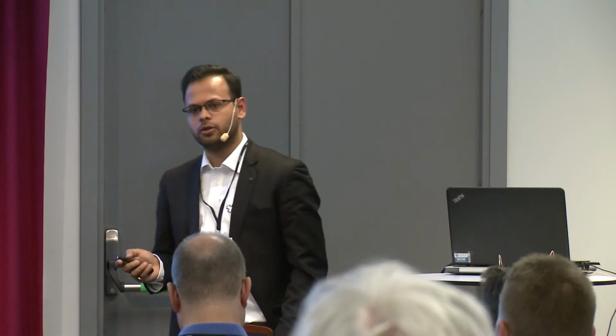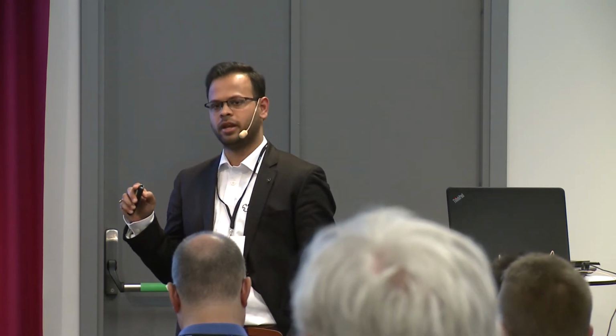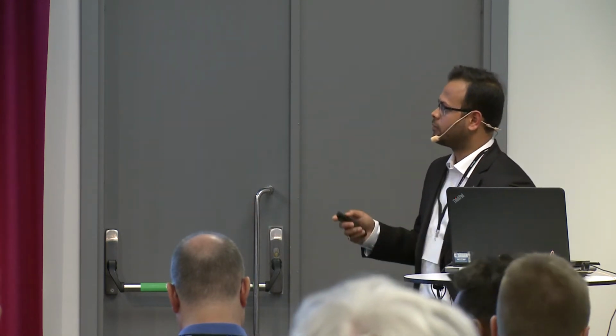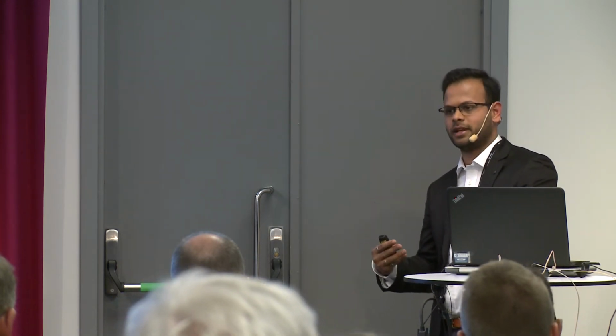But the analysis from the last 5 years has shown that converters are the main source of downtime and problems for wind turbine operators. So what we are looking into now is making a solution right from sensor to the maintenance recommendation and failure prediction platform, which can be made for these wind turbines. This is a research and development project which is being funded by the EU. And we have already got some interesting insights, like very specific parameters which need to be measured in order to predict the failure. Because you cannot just stream all the data which is possible and then start analyzing. It's important to involve domain expertise.